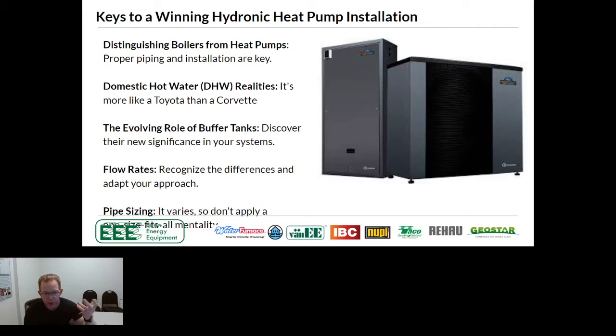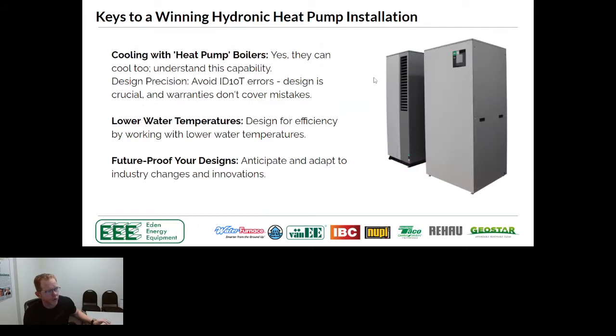The other thing we want to recognize is the difference in flow rates and pipe sizing. So I talked at the very first about distinguishing between them and piping them properly. We need to understand that hydronic heat pumps have different flow requirements. And because they have different flow requirements, it's also important that we make sure that we pipe them accordingly.